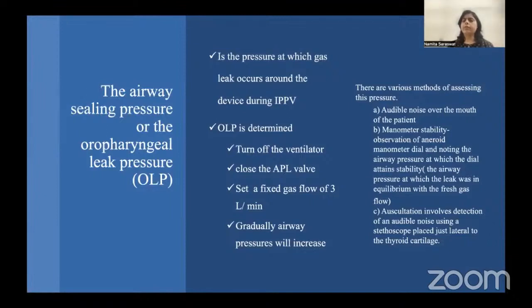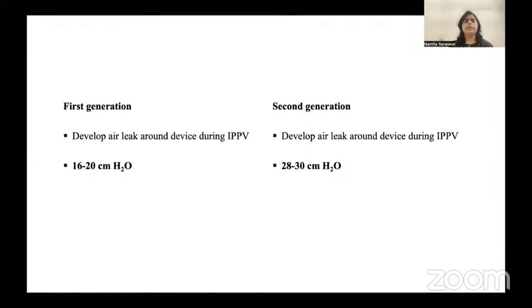First, audible noise can be heard over the mouth of the patient. Second, you can connect the manometer and observe the manometer stability. Observe the aneroid manometer dial and note the airway pressure at which the dial attains stability. What does it mean? That is the airway pressure at which the leak is in equilibrium with the fresh gas flow. So a constant pressure will be seen on the monitor, and that will be the oropharyngeal leak pressure. Or you can auscultate to detect the audible noise using a stethoscope placed just lateral to the thyroid cartilage. First generation devices have an oropharyngeal leak pressure of around 16 to 20 centimeter of water, and second generation devices are better than first generation, around 28 to 30 centimeter of water.